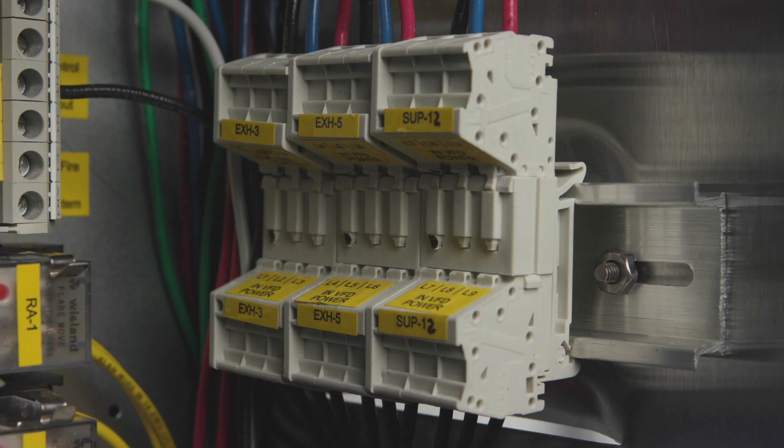For example, here's the wiring for an exhaust fan being controlled by VFD. You see here, the high-voltage wiring comes from the breaker in the building's breaker panel to terminals L1, L2, and L3 in the control package. These terminals are located here.